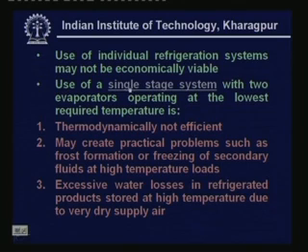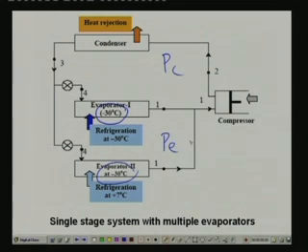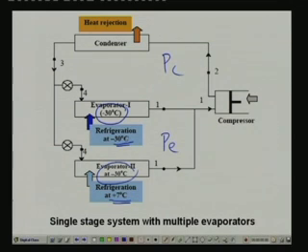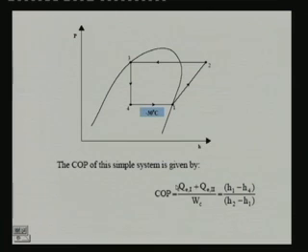In a simple single-stage system with two evaporators, both evaporators operate at the same temperature since a single compressor is used with no pressure-reducing valve. Both operate at the evaporator pressure Pe corresponding to minus 30°C. The only two pressures are condenser pressure Pc and evaporator pressure Pe. The COP of this system is simply the refrigeration effect H1 minus H4 divided by the work of compression H2 minus H1.